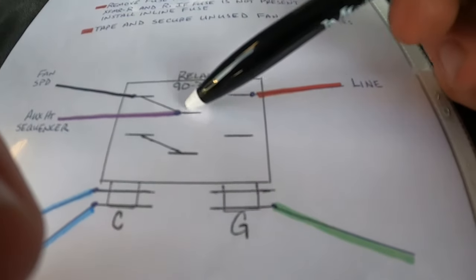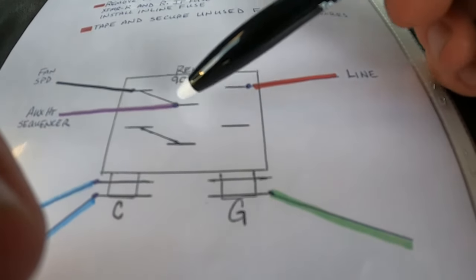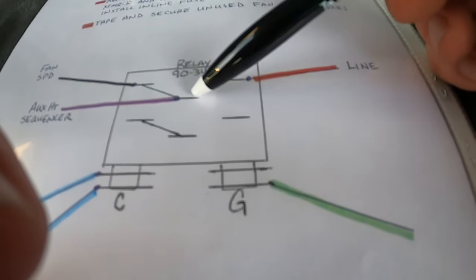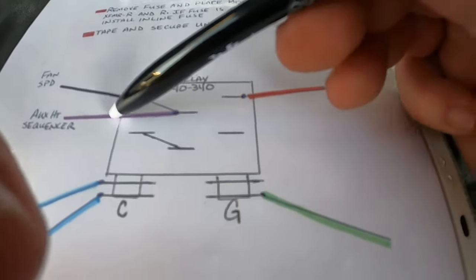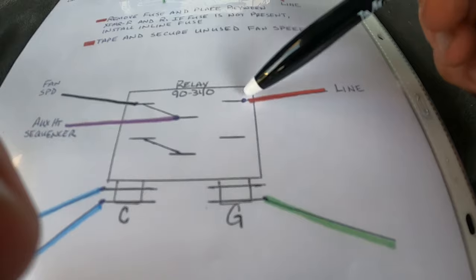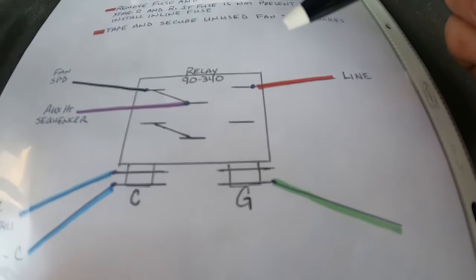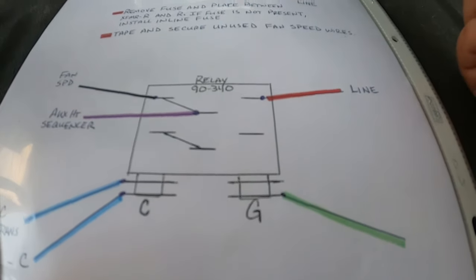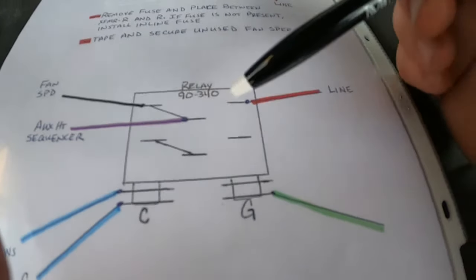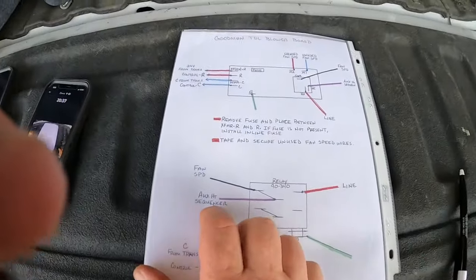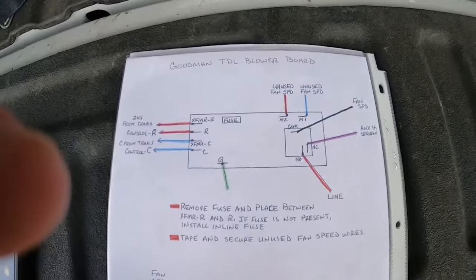If you get a call for G, that switch is going to close to here, open that circuit so you don't get power going back, energizing your heat coil. It's going to run the blower in normal heating and cooling operations.